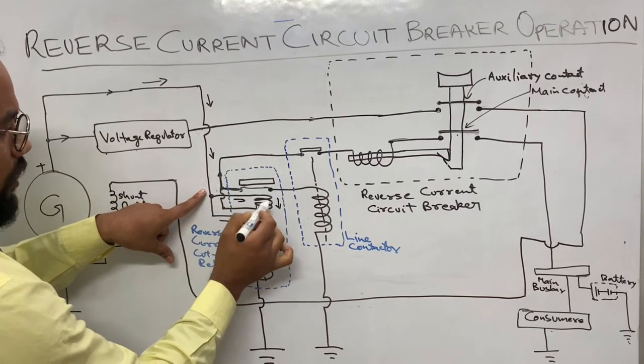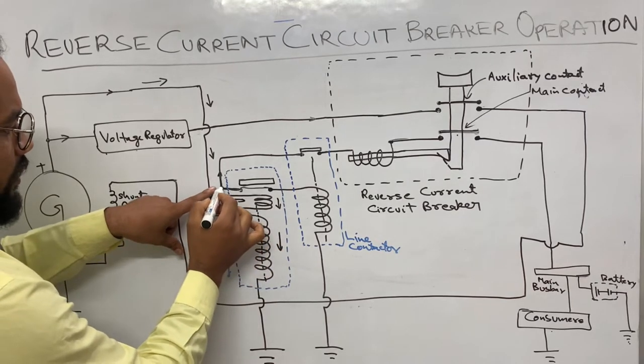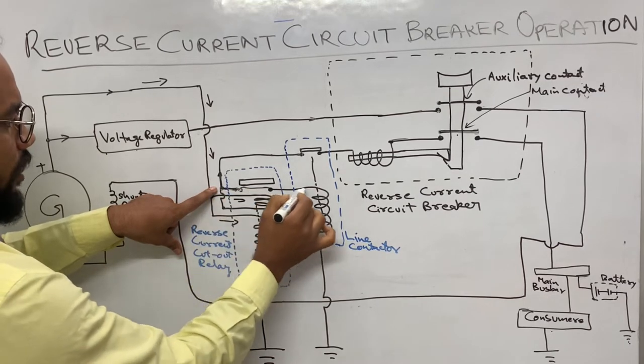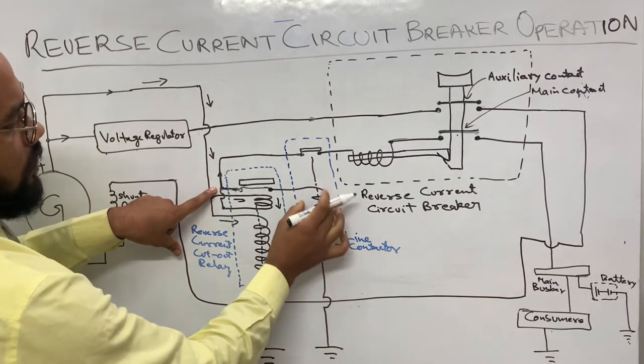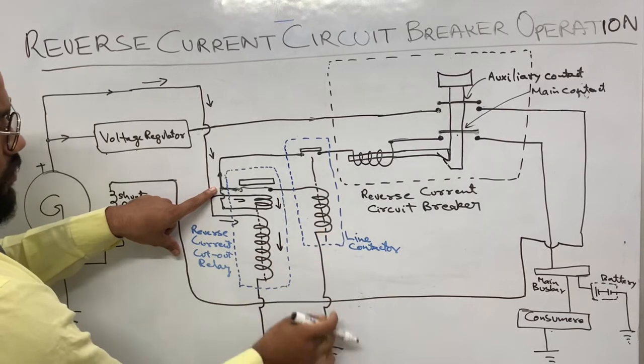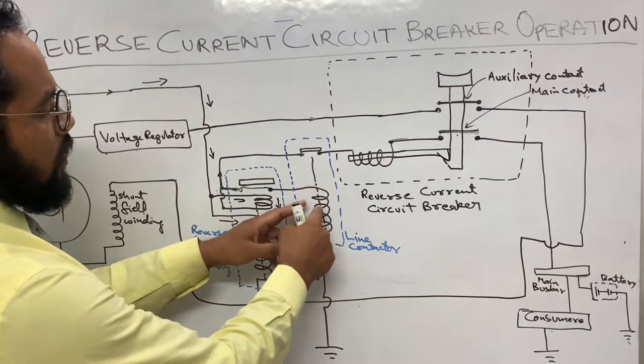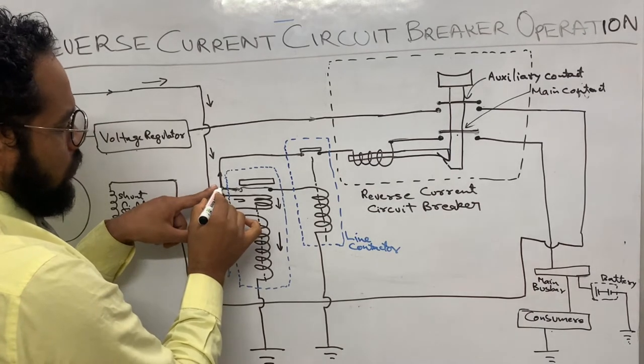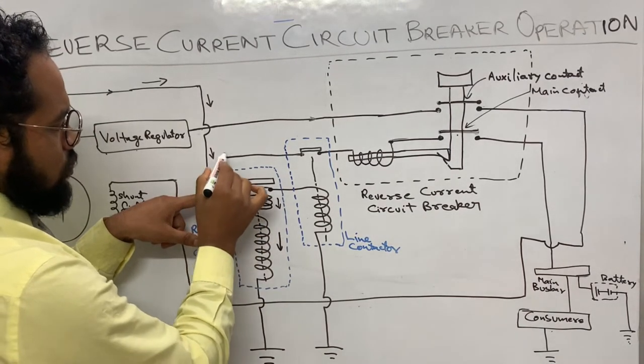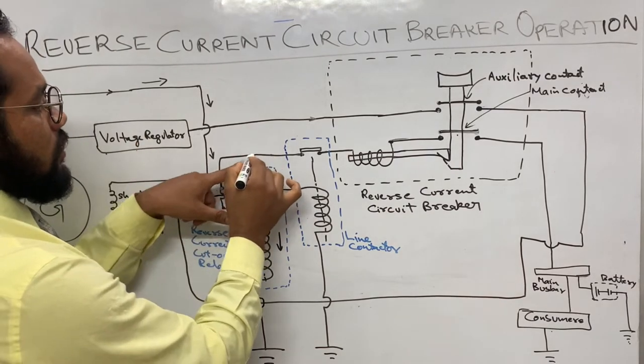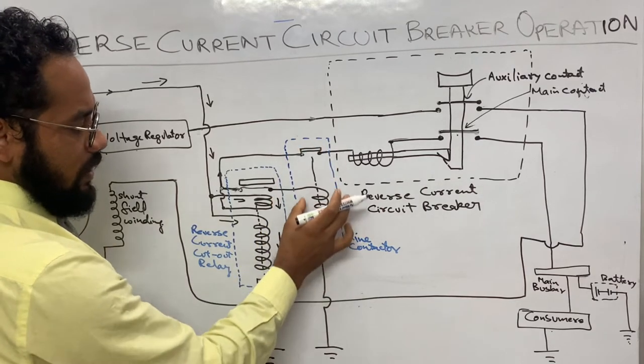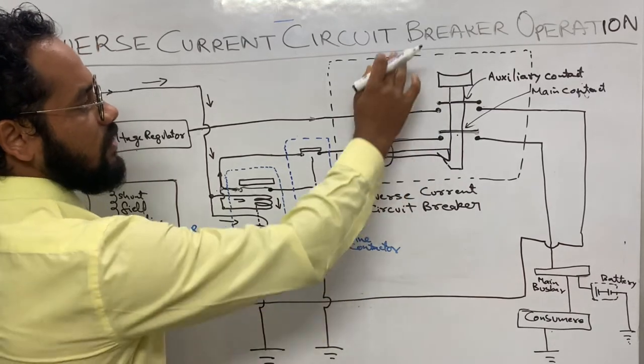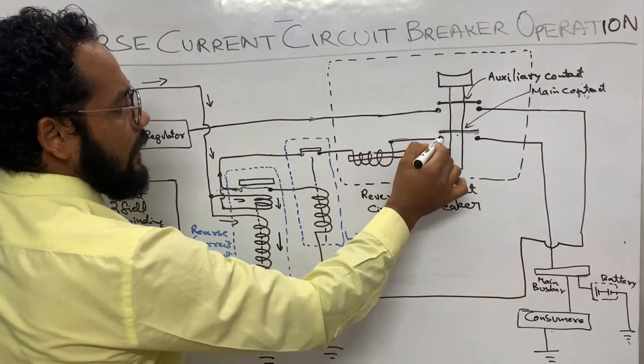When this contact is closed, the current also goes to the current coil. The current splits — it goes through this path and that path. Through one path the current goes and energizes the coil of the line contactor. When the line contactor coil gets energized via its grounding path, the line contactor contact closes. Now whatever current was at this point from the current coil will go ahead through the magnet system coil of the reverse current circuit breaker.